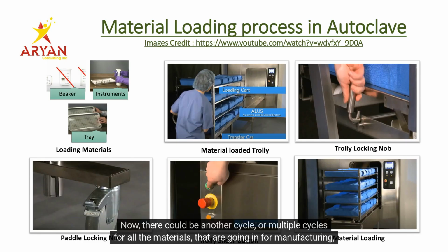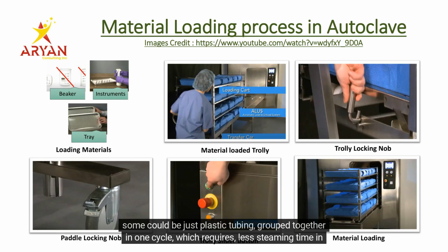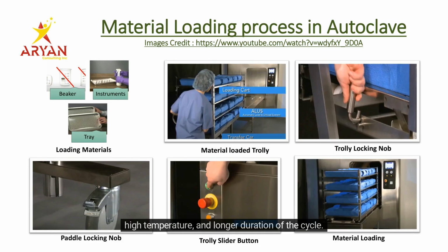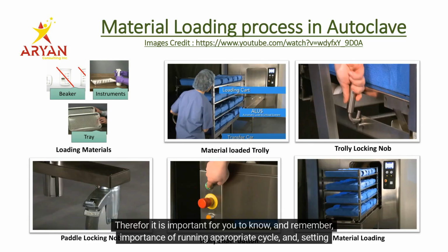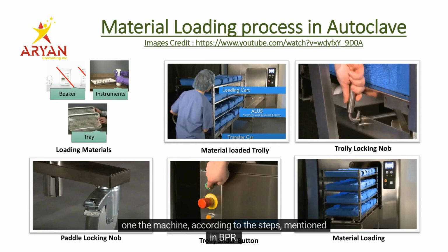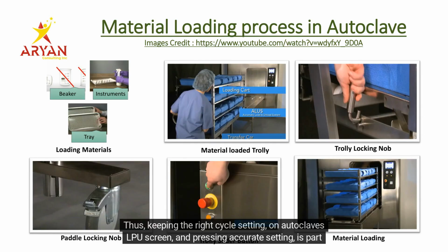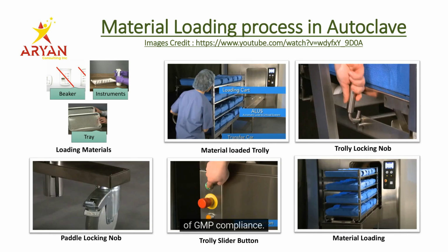Now there could be another cycle or multiple cycles for all the materials that are going in for manufacturing. Some could be just plastic tubing grouped together in one cycle, which requires less steaming time, in comparison to all metal items grouped together in a different autoclave cycle setting with slightly higher temperature and longer duration. You got the point. Therefore, it is important for you to know and remember the importance of running the appropriate cycle and setting the machine according to the steps mentioned in the BPR. Thus, keeping the right cycle setting on the autoclave's LPU screen and pressing the accurate setting is part of GMP compliance.